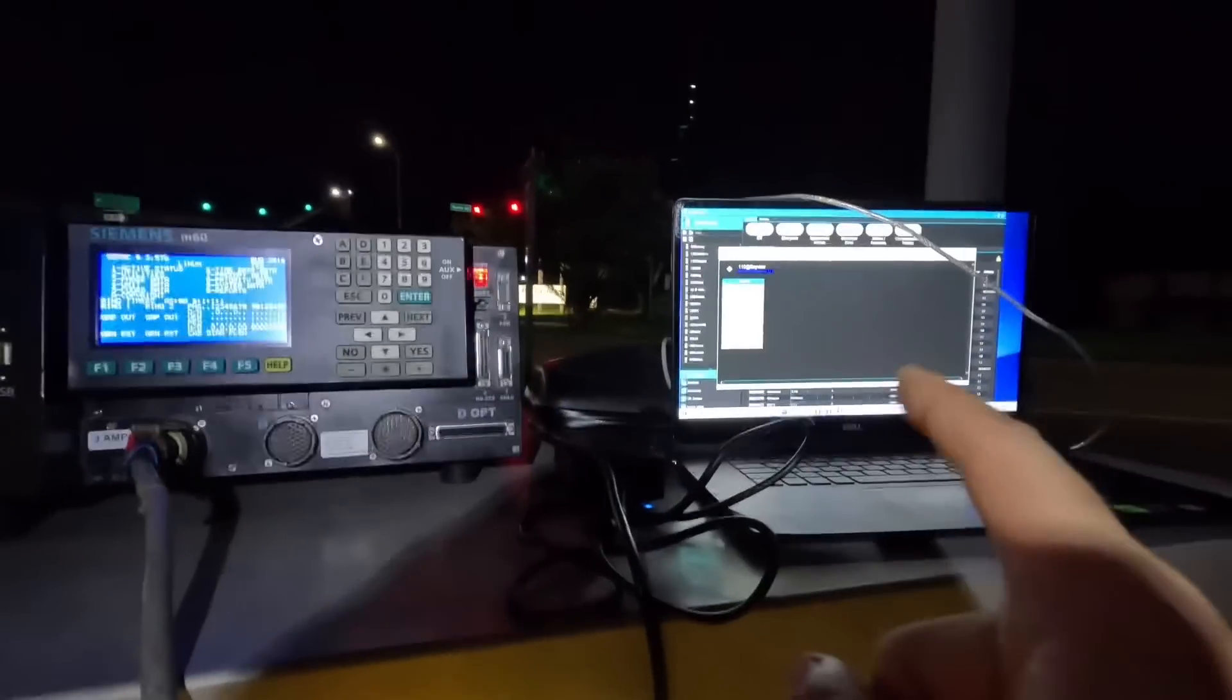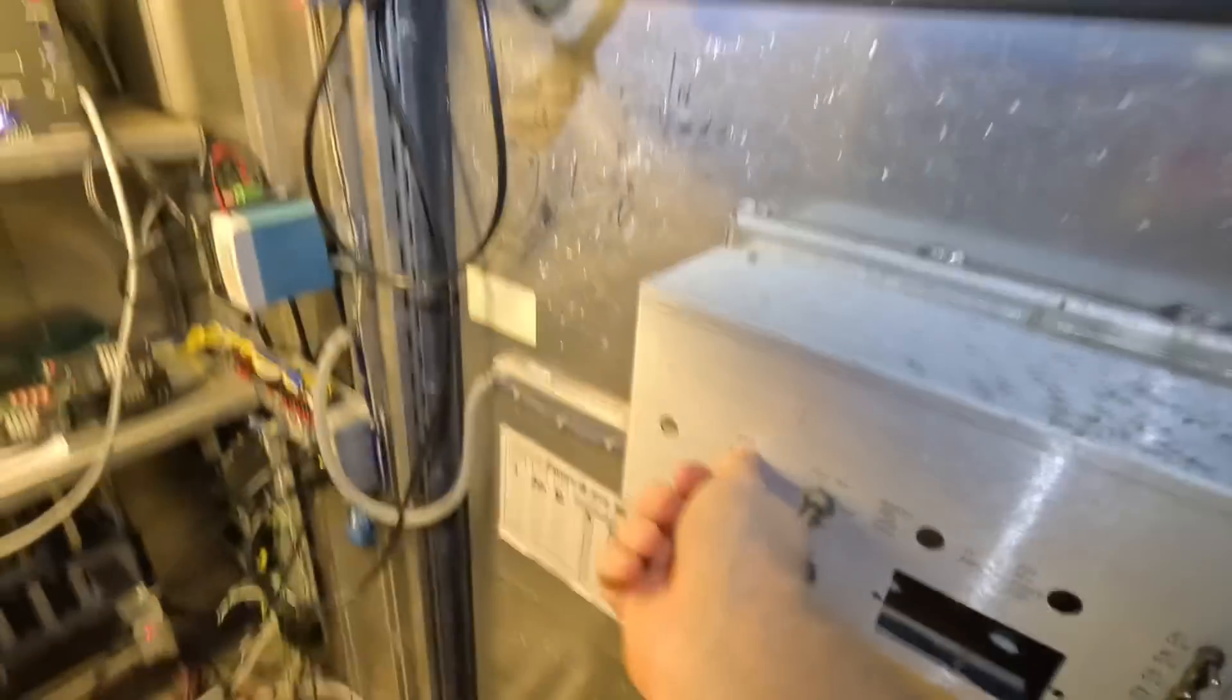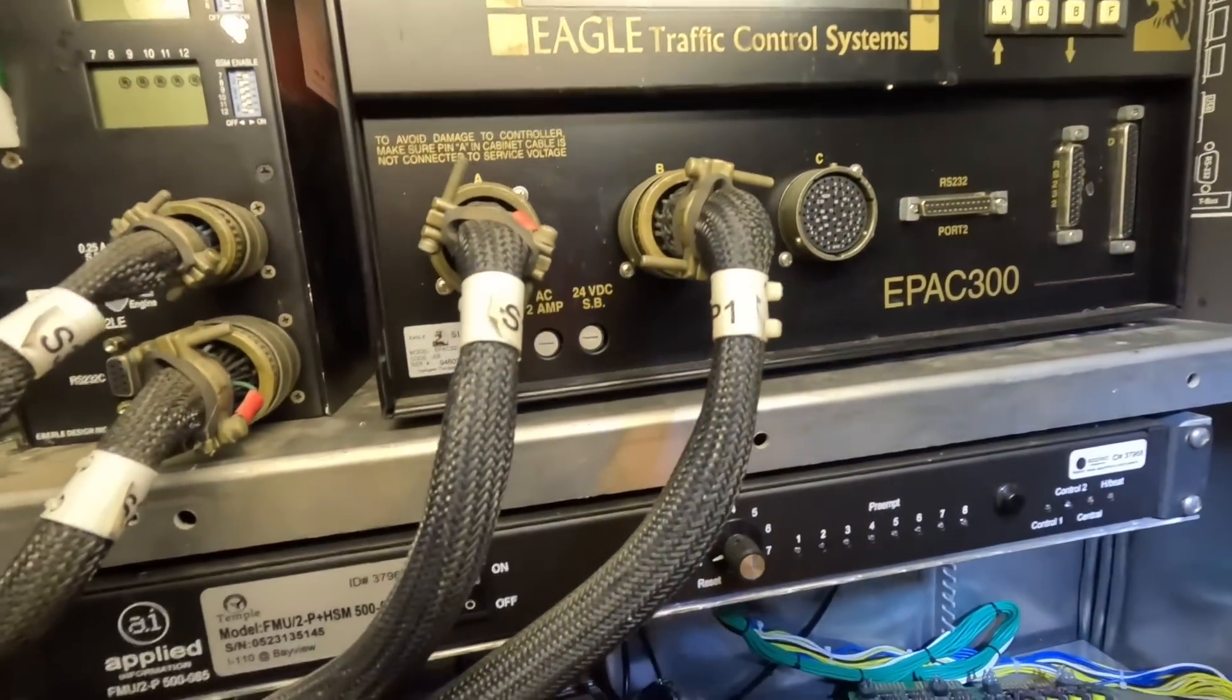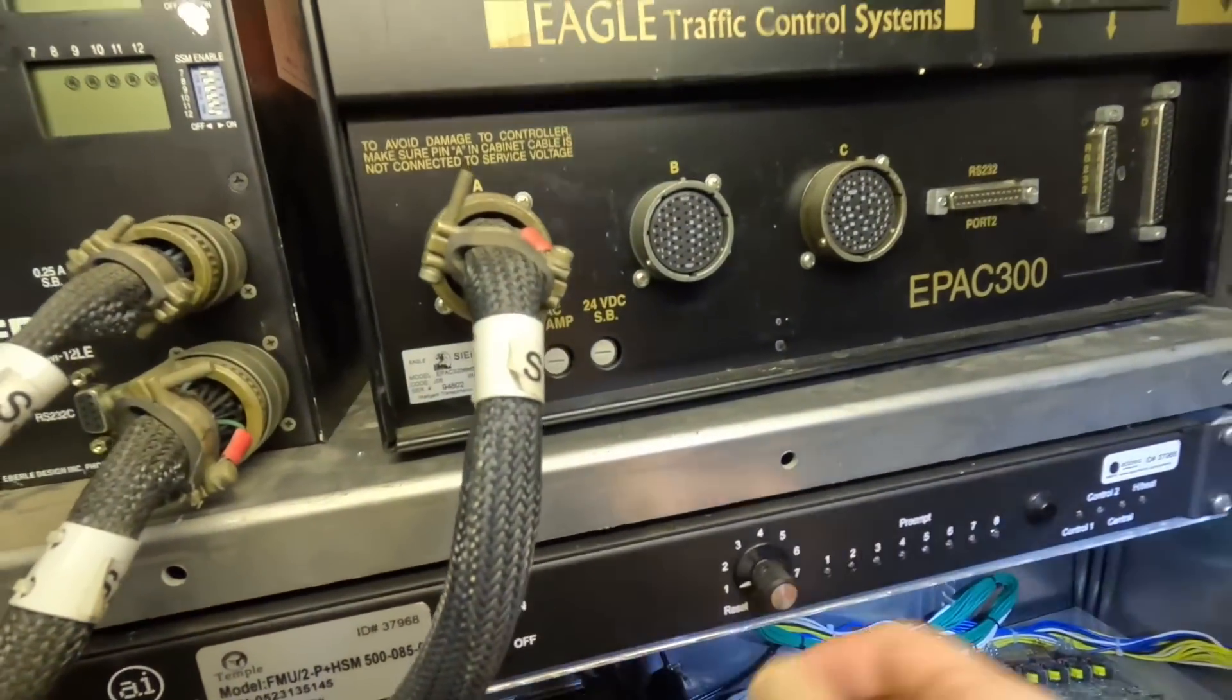All right, so now all the data from the laptop that's from the old controller has been moved over to this controller. We can go ahead and pull out my power cable from this controller here. Now we can go ahead and put the intersection into flash. There is cross traffic, but he's got the green light and he's going through it. So let's put the intersection into flash. It's now flashing out there in the field, and we can go ahead and start disconnecting this controller here. Let's rip these pin connectors out.